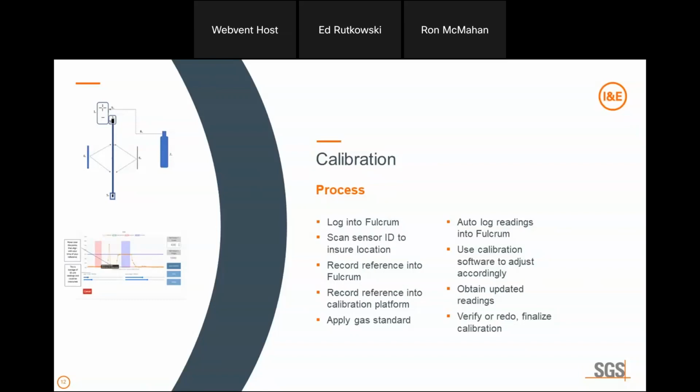And now we recorded what the response was on the instrument without any calibration yet. So what was the instrument reading when we got to the room? We applied the 1,000 and the 5 ppm respectively. What did it read? And we recorded that so we could look at what the accuracy was of this instrument basically during the last year.